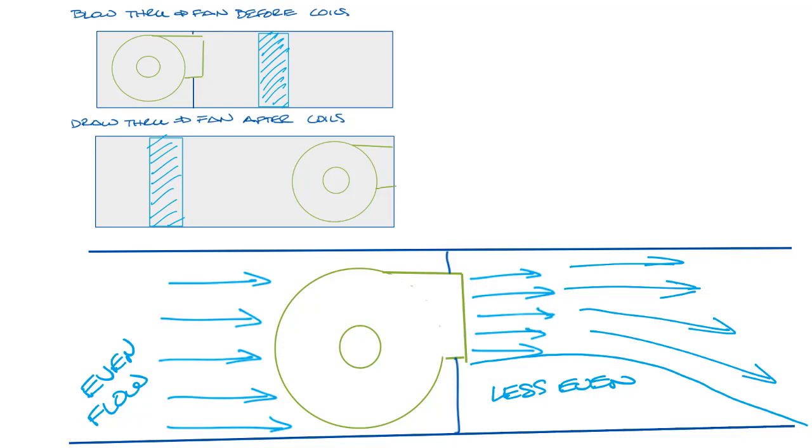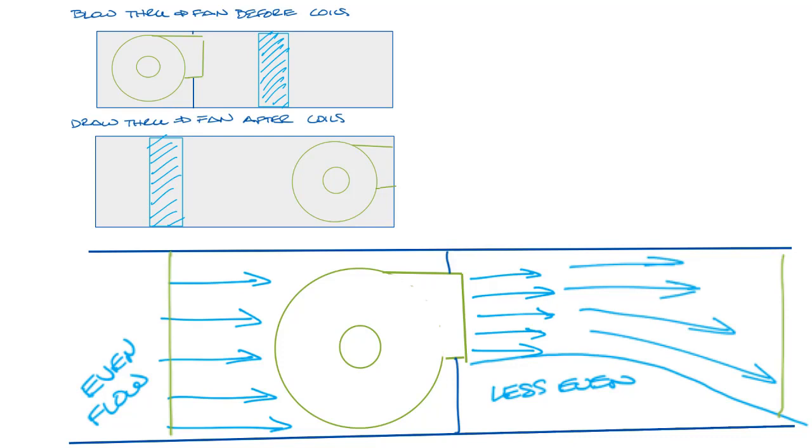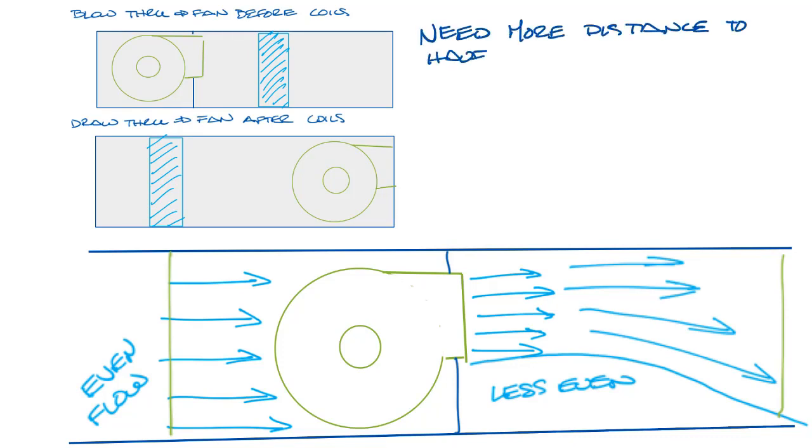So if your water coil is located on the inlet side in a draw-through application right here, it has much more even air flow. In a blow-through application, to get to the point where you have even air flow, you'll need to put more distance between the discharge of the fan and the water coil.